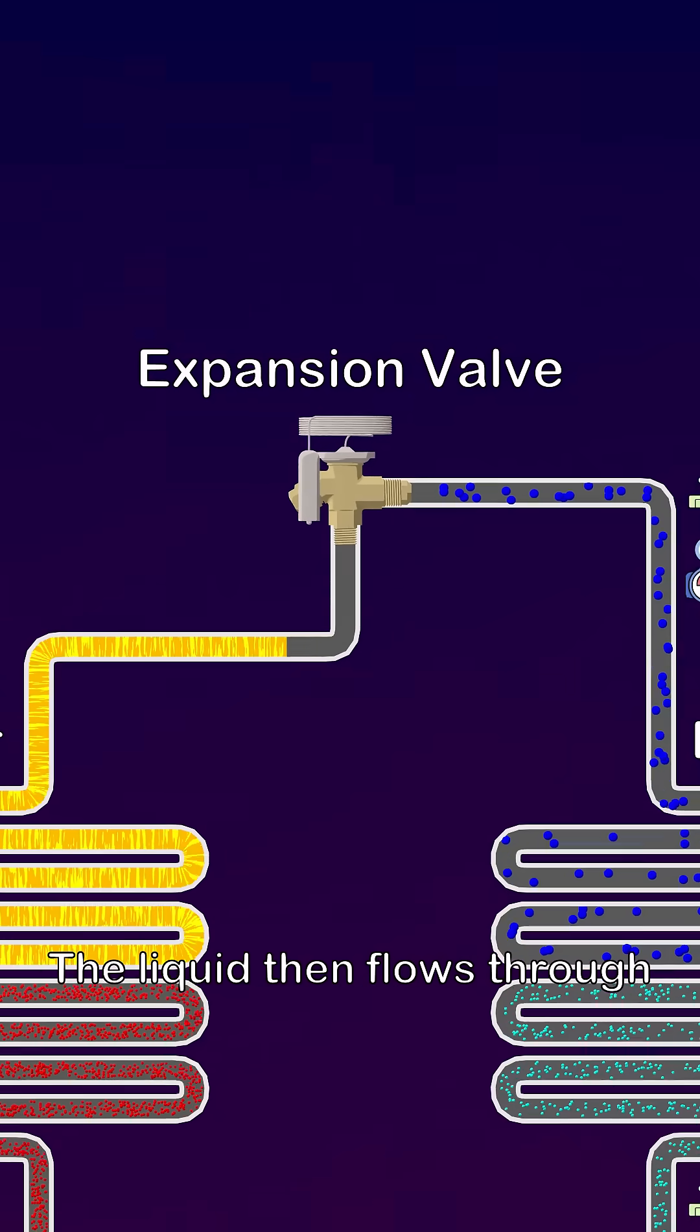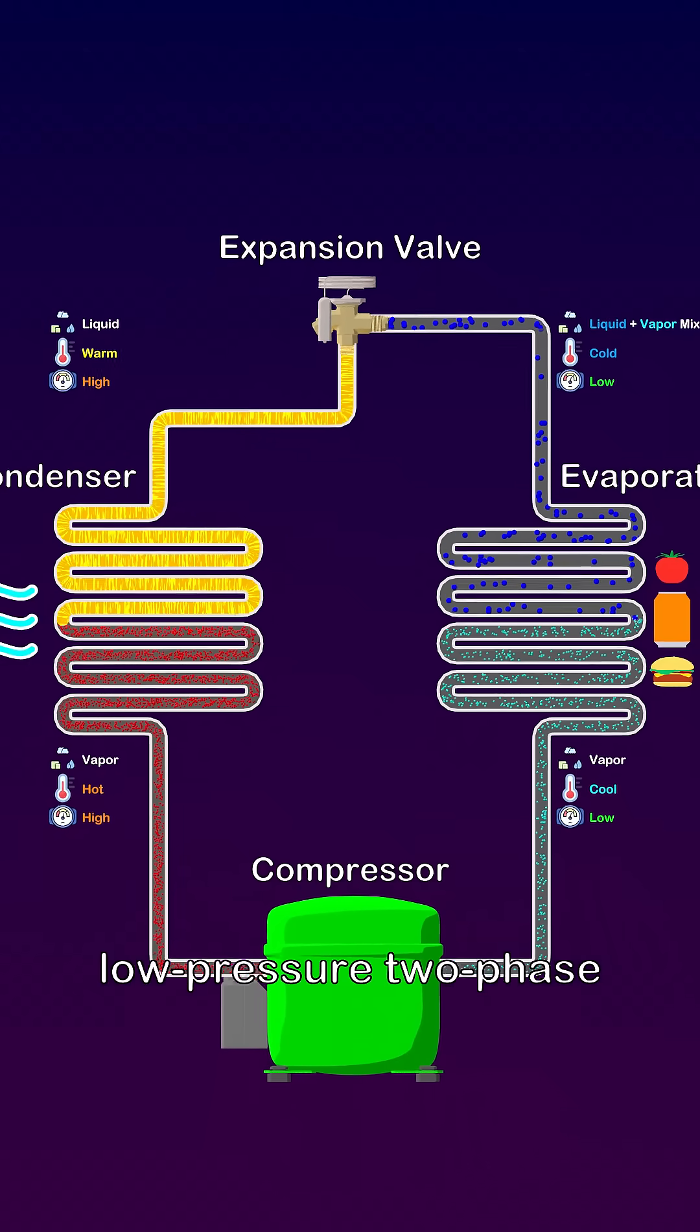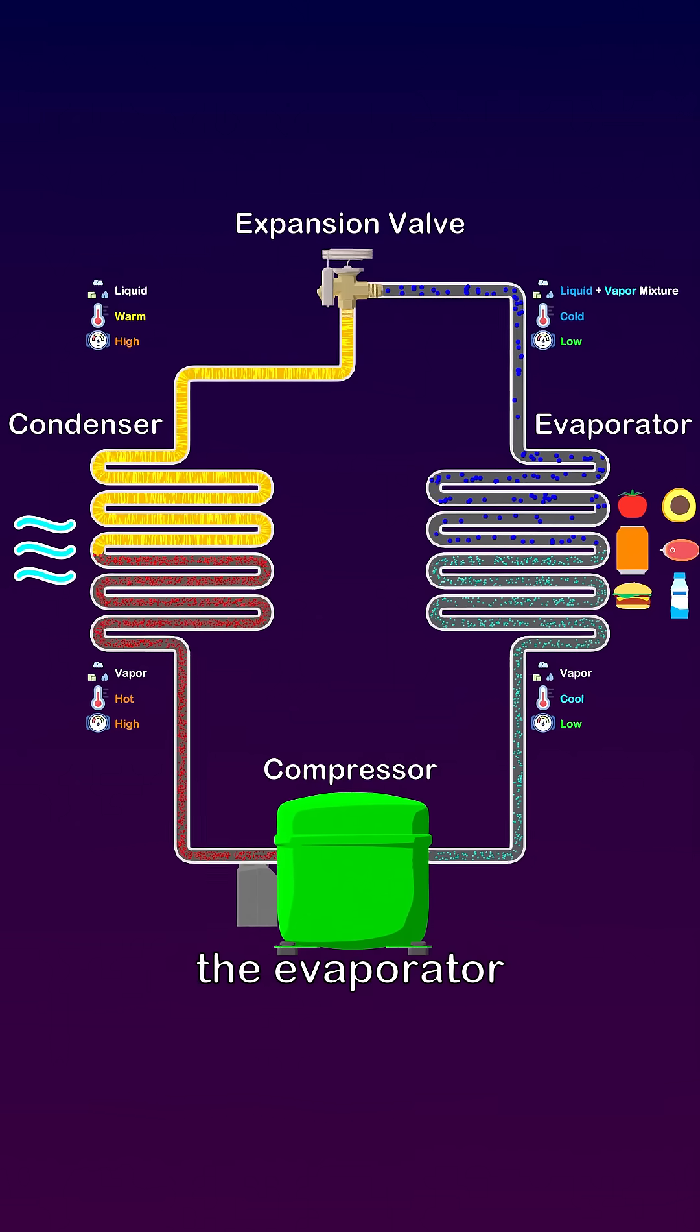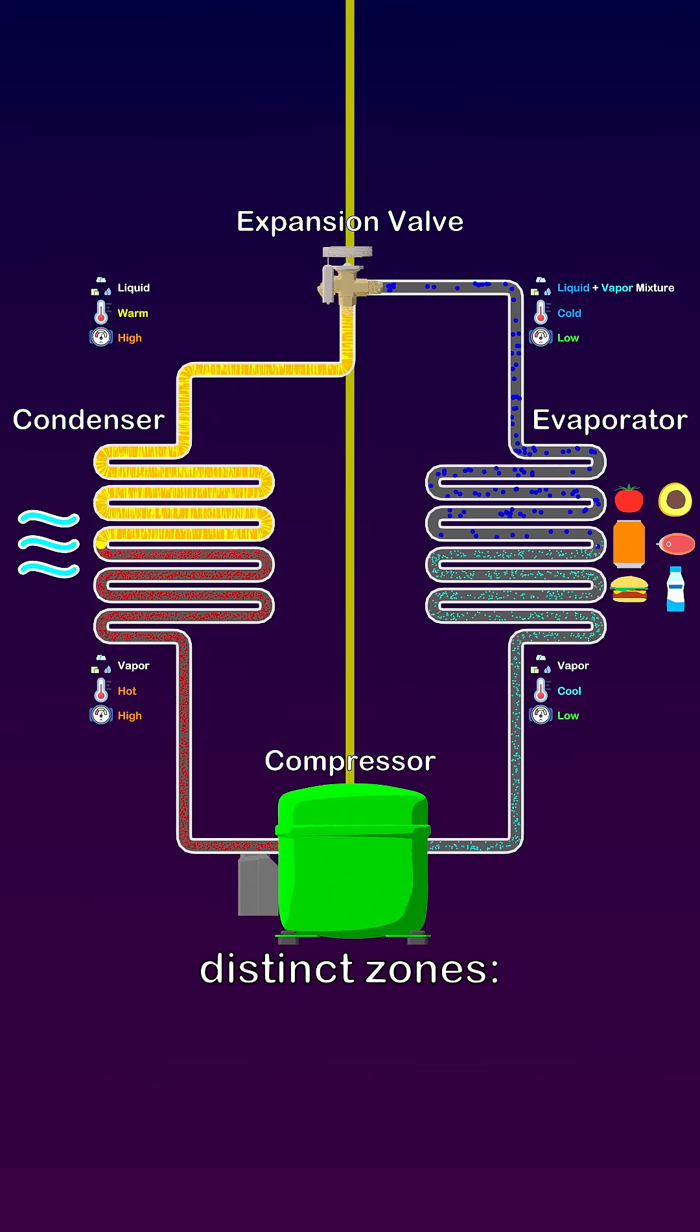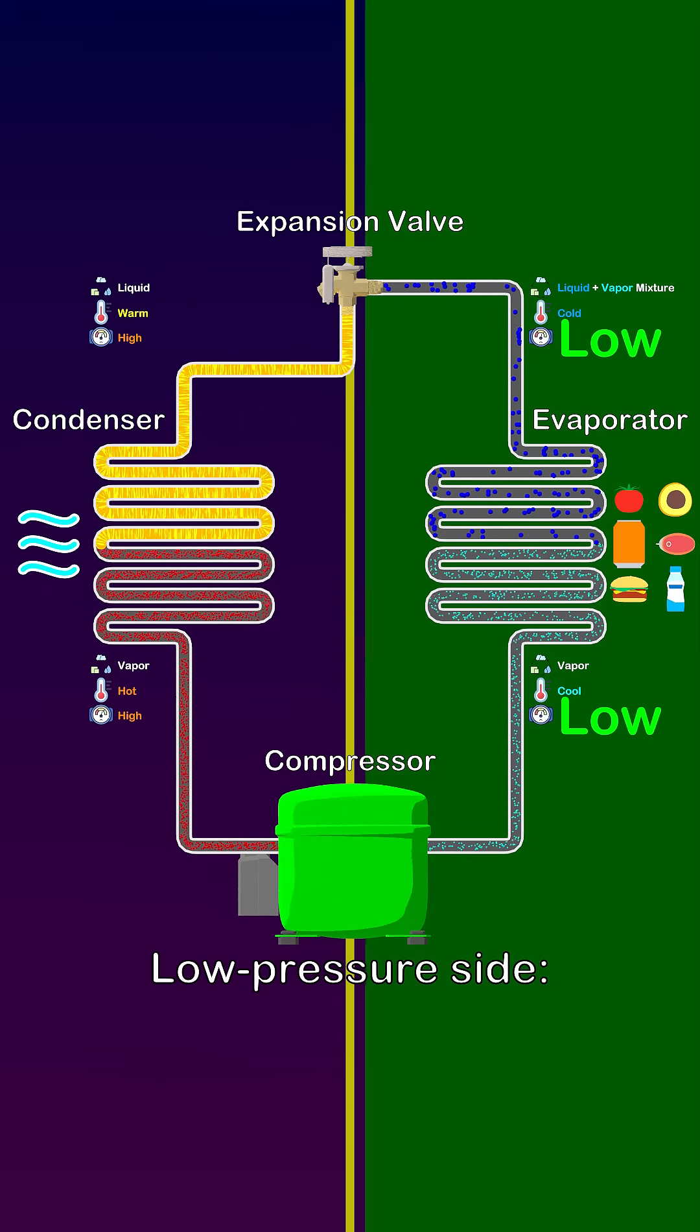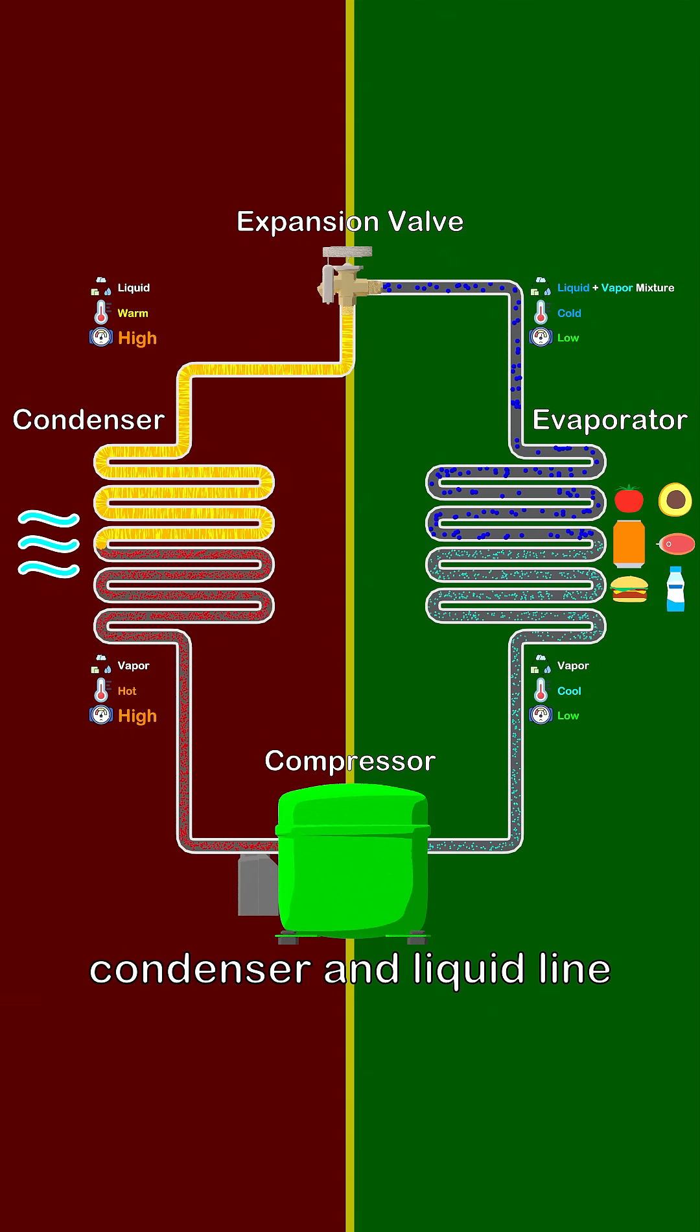The liquid then flows through the expansion valve, where it undergoes a sudden pressure drop and becomes a cold, low pressure two phase mixture, which is sent back into the evaporator. The compressor and expansion valve divide the system into two distinct zones. Low pressure side: evaporator and suction line. High pressure side: condenser and liquid line.